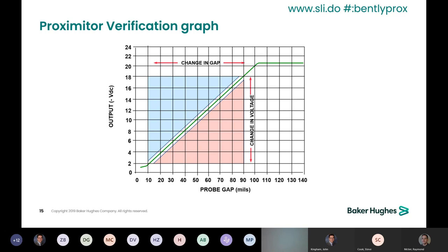The overall average scale factor is an important tool for evaluating the performance of the transducer systems. In addition, the incremental variances are important as well. When response is evaluated, it should show little deviation from the ideal linear response curve shown here. The API 670 conventions have specifications for both the overall scale factors and the incremental variances.